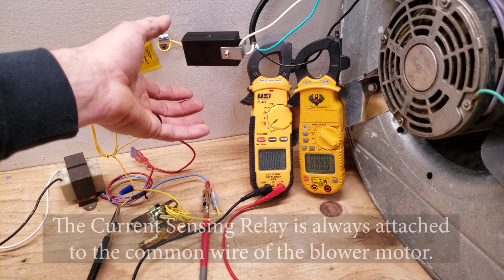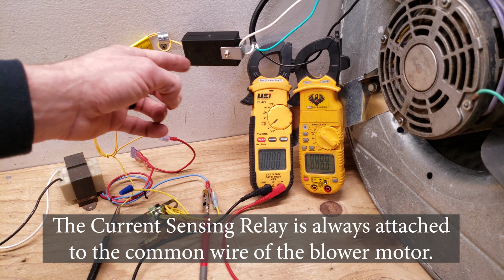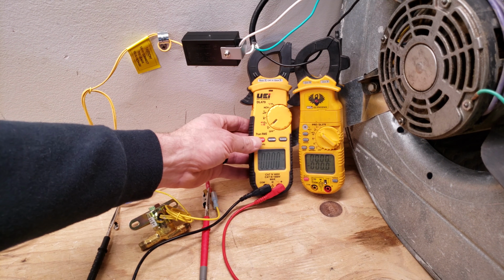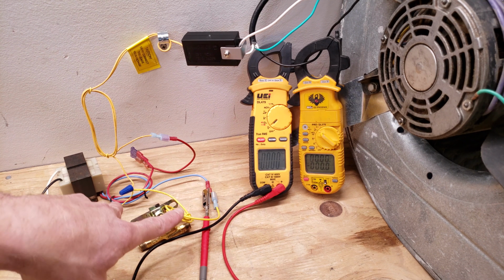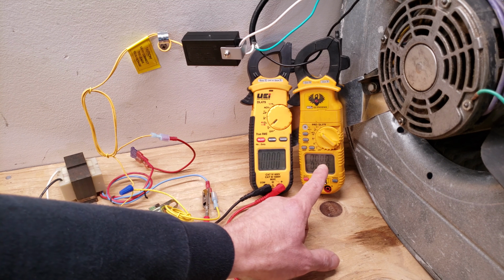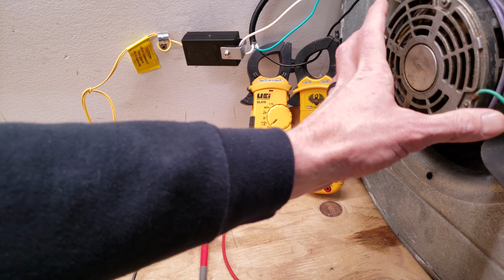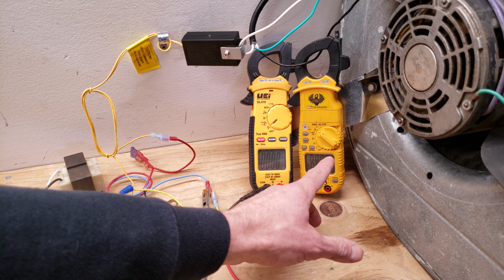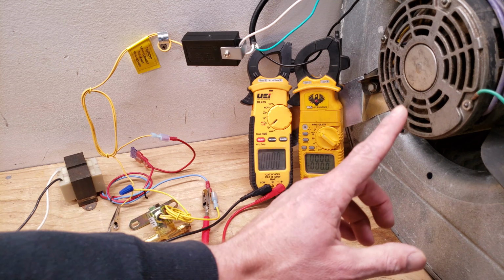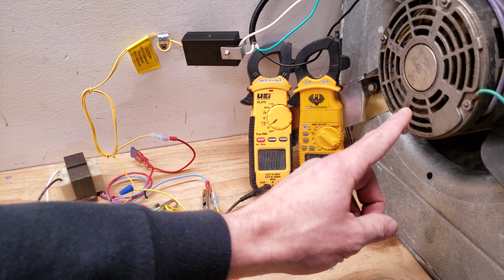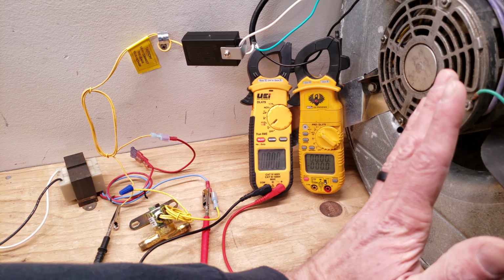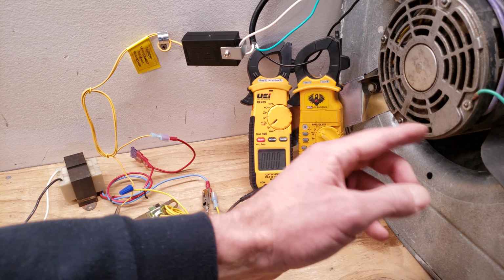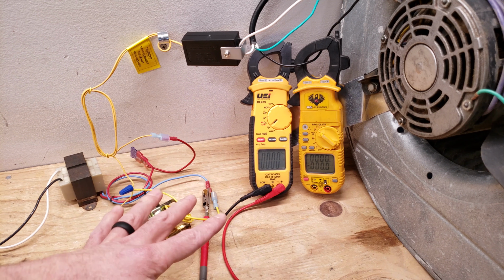I'm going to show you that it's actually going to be allowing the 24 volts through at an even lower amperage. So with this one right here, we're going to measure our voltage going to the solenoid, and we're going to be measuring the amperage that our blower motor's drawing right here. The way I'm going to adjust the amperage being drawn by the blower motor is by shutting off the airflow. I'm going to be closing off how much airflow this blower motor is able to push. So that's what's going to happen.